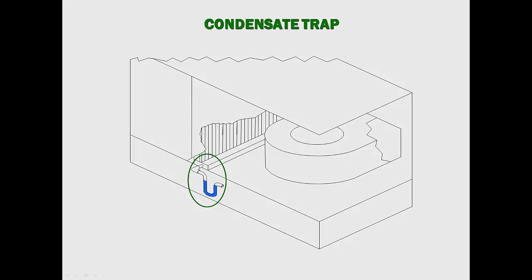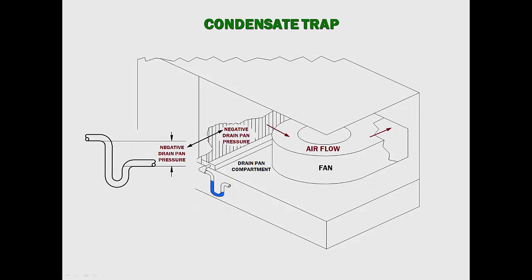In the industry, the most commonly used drain seal is the condensate trap, installed on the drain connection as illustrated. It uses water to form the drain seal. In theory, the design and operation is simple. The geometry of the trap is determined by the negative pressure created in the drain pan compartment by the fan.